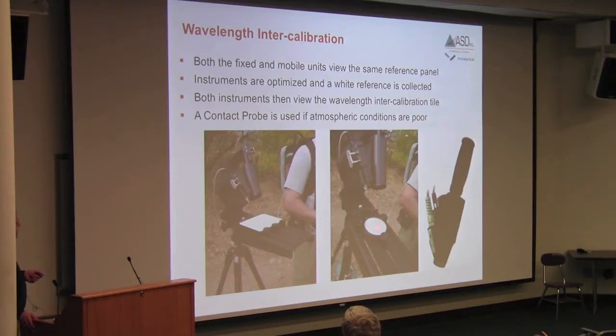If you want to be more careful about it, a lot of the systems have what's called a contact probe that has a light source built in. And if you don't want to worry about light conditions for the wavelength scale intercalibration, you do get a little better results by using the contact probe, though again, you'd have to move the fiber optic of the two instruments back and forth. So you make the wavelength measurement using that accessory.